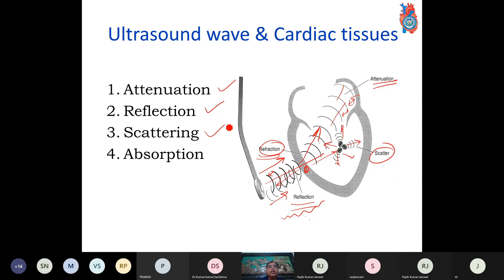And the fourth one is attenuation. The tissues reduce the intensity of the wave. They absorb the ultrasound waves. So the amount of waves coming back is attenuated. You see the amount is reduced. What the wave started with from here was this much frequency, and there is attenuation of the intensity of the wave. So these are the four components of how ultrasound waves, when generated from the transducer, go to the structures and come back. Attenuation means the medium absorbs it. Reflection, they are reflected away. There's scattering and there's absorption.